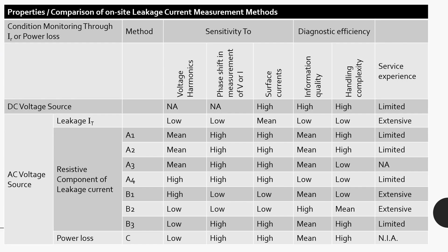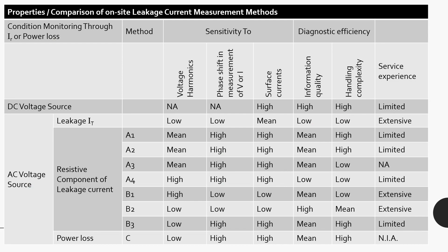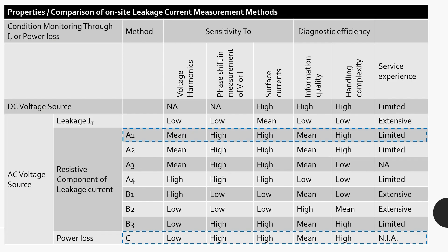For lab scale testing, the preferred option is method A1 which is measurement of current at voltage peak, and method C which is watt loss measurement using integration of current and voltage over one cycle. Of course, these are the two of my preferred choice for condition monitoring.